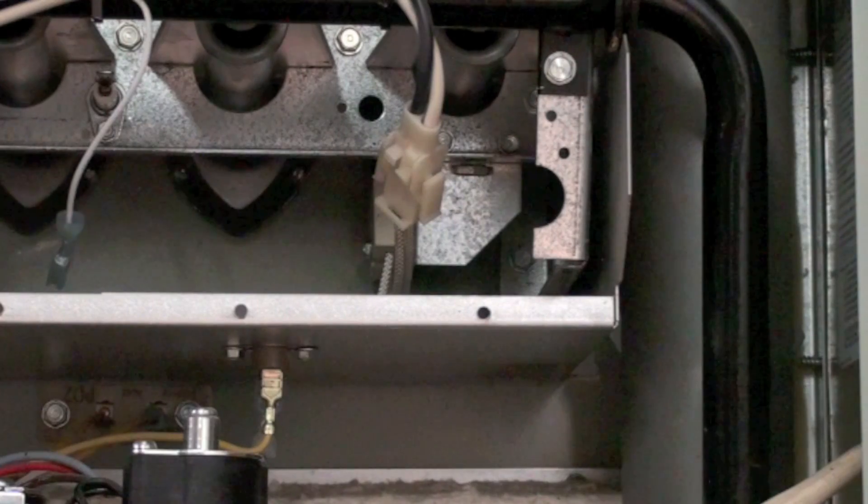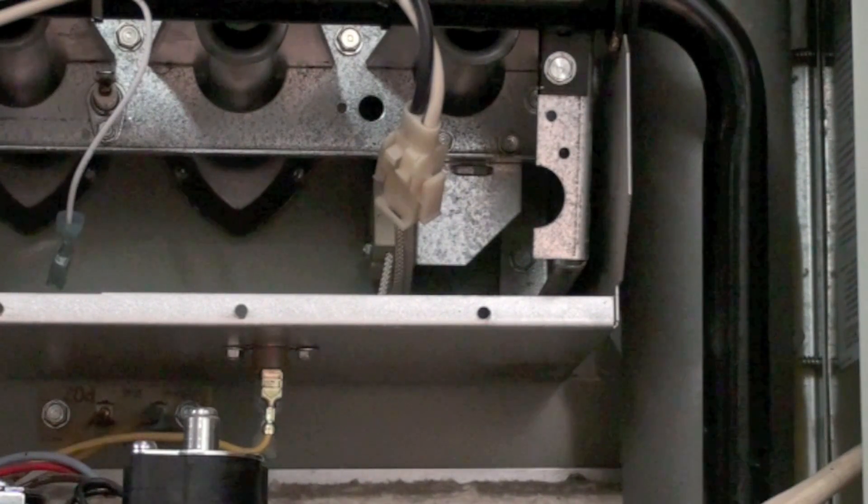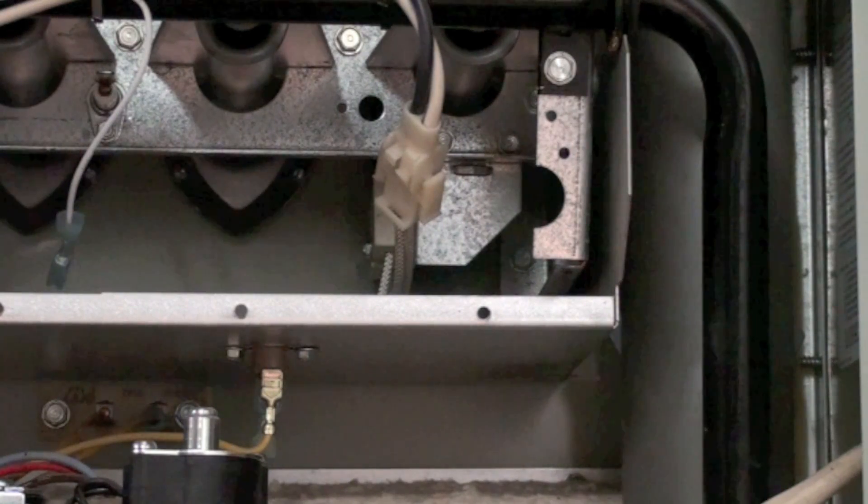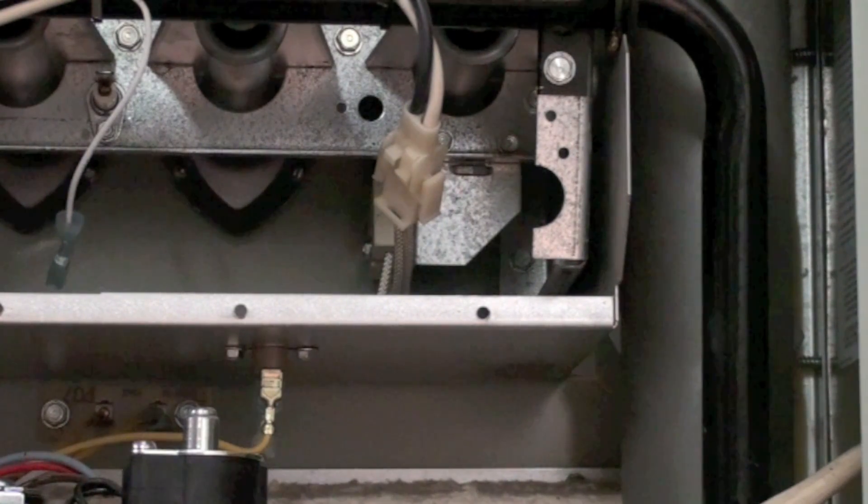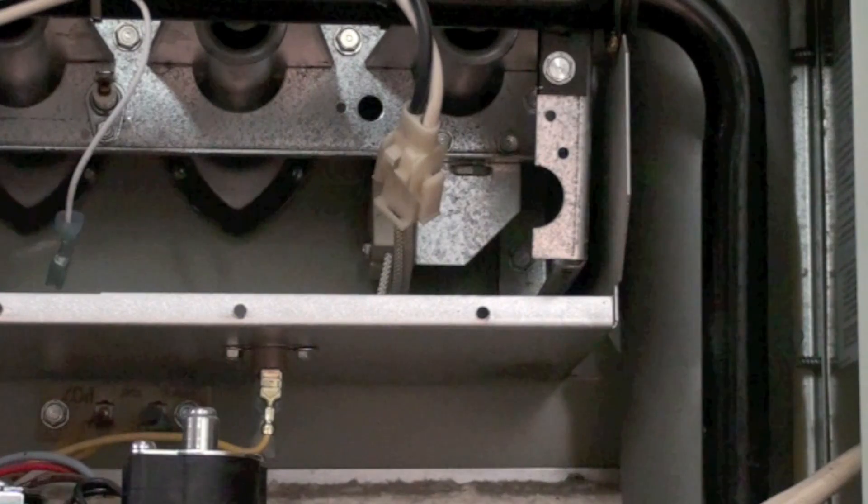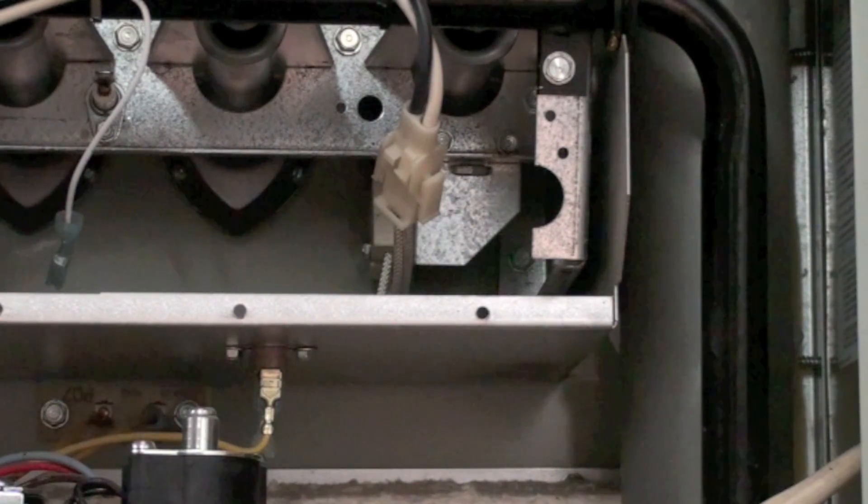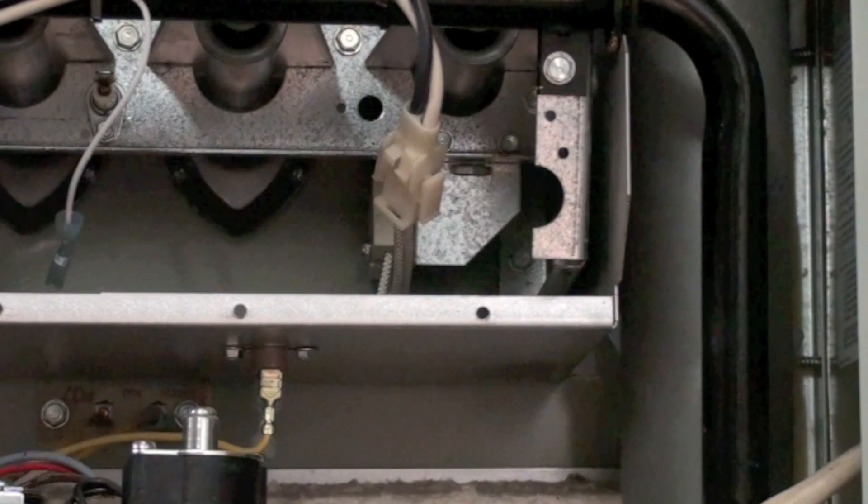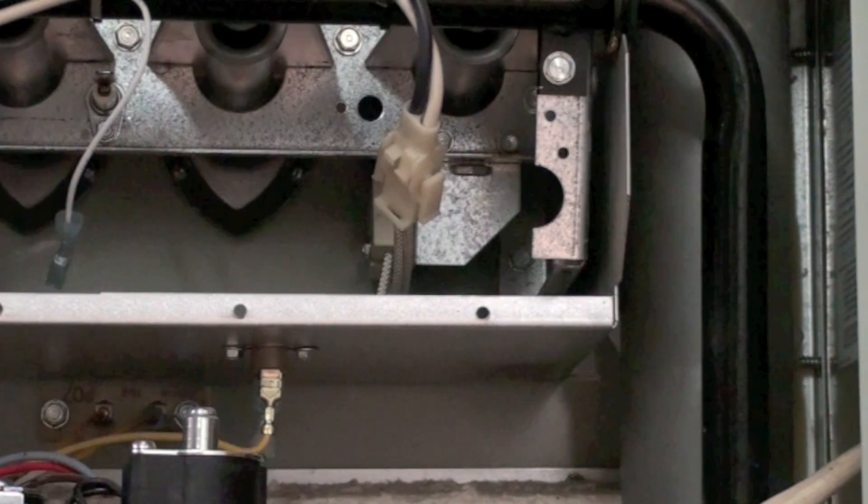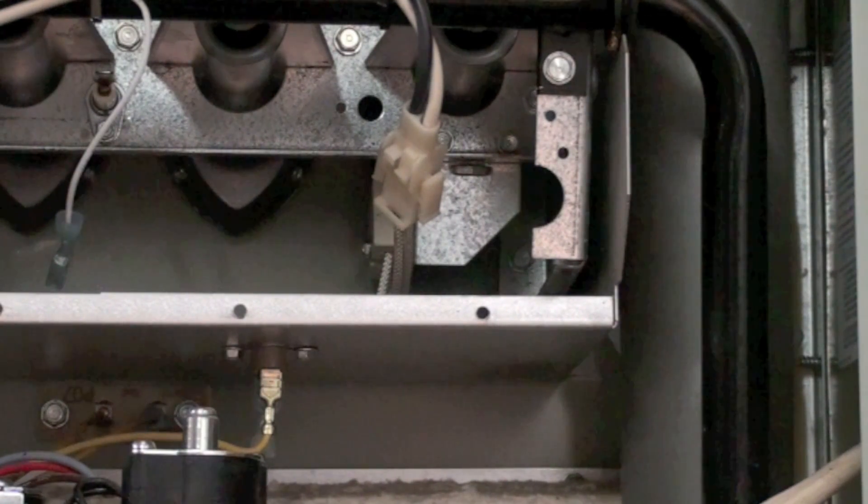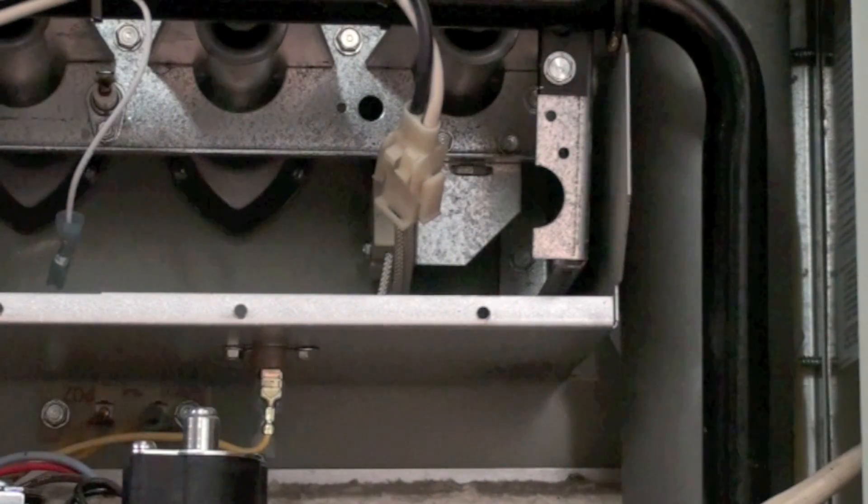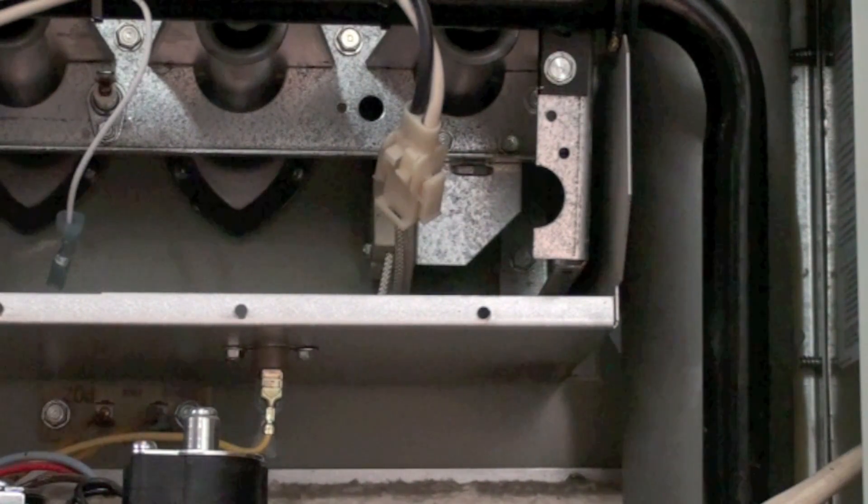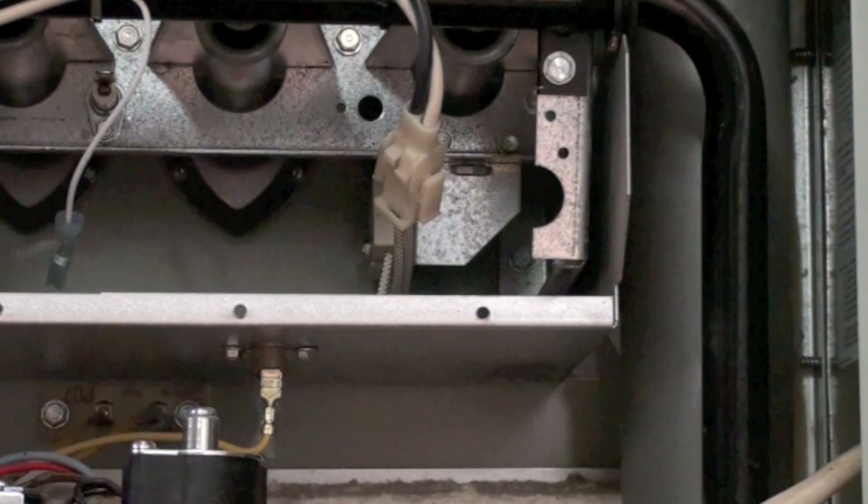Common symptoms for this were people would wake up in the morning, the furnace isn't working. They turn the power on and then back off again, or off and back on again, and it would start up. They come home from work and it's not working and they do that again, and usually it gets worse. It works very simply. That flame rod is not sensing flame, it does not get the microamps it needs, so it shuts it off.